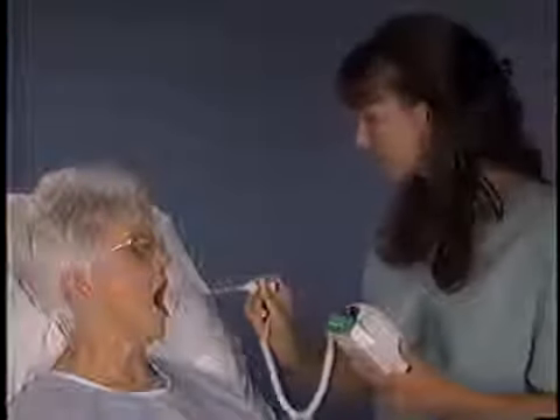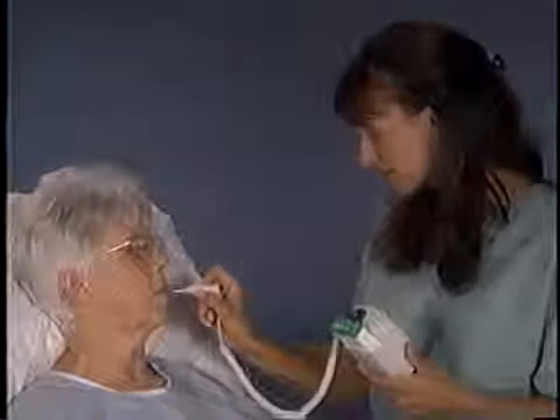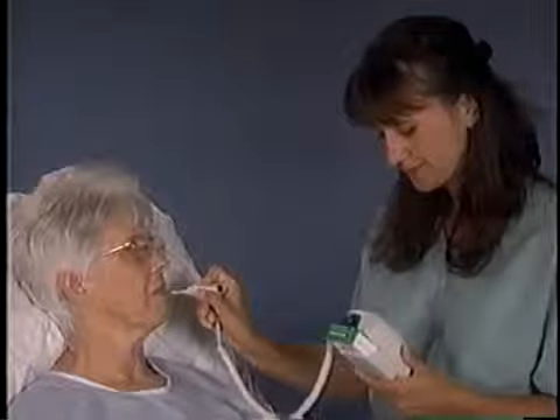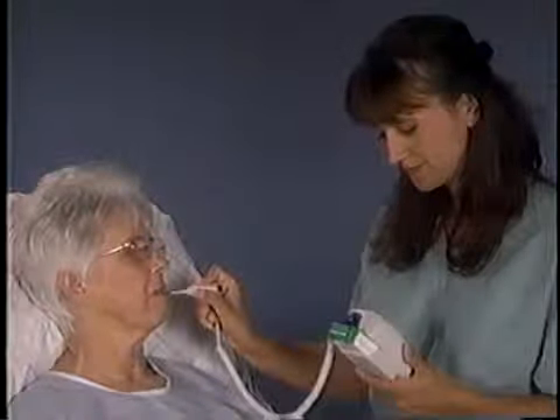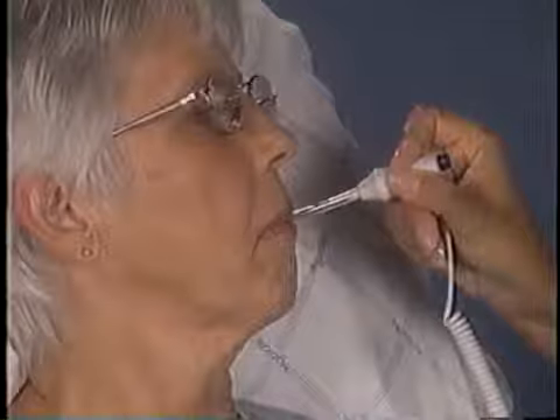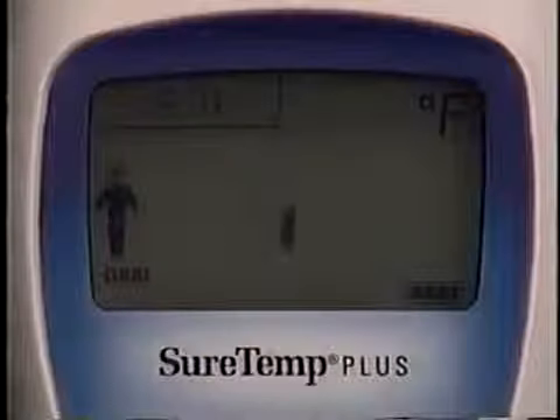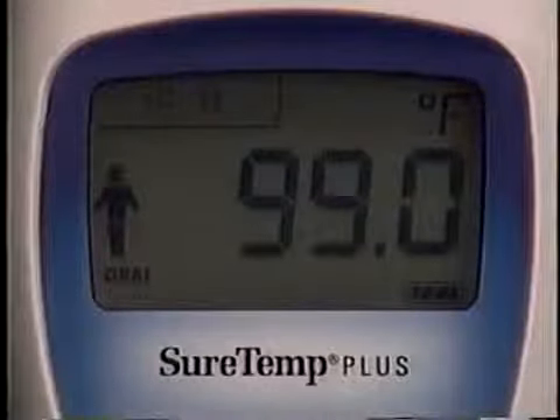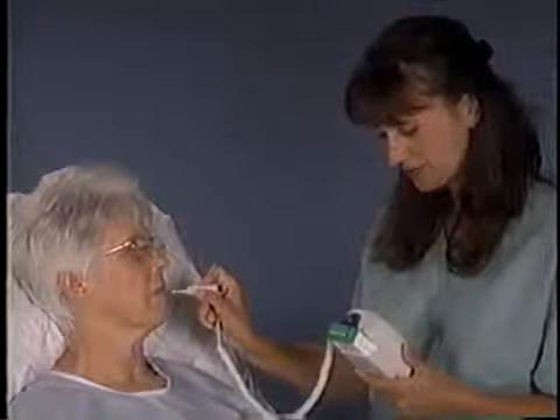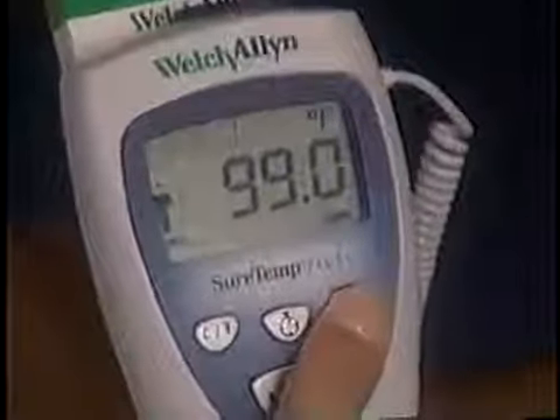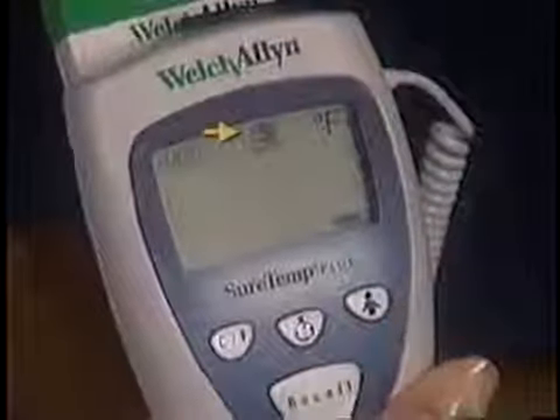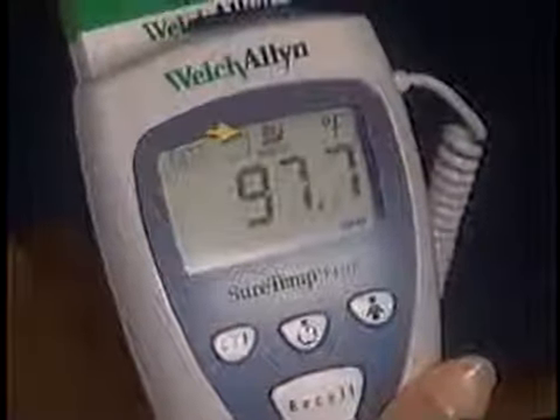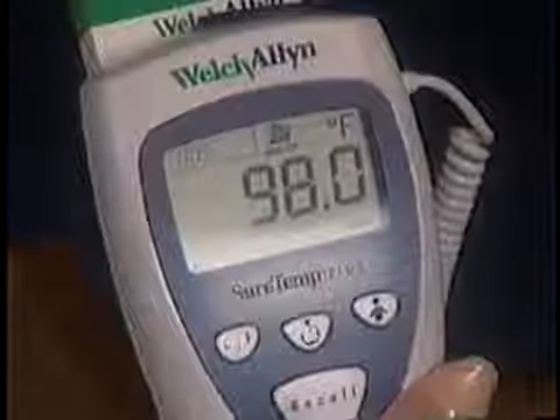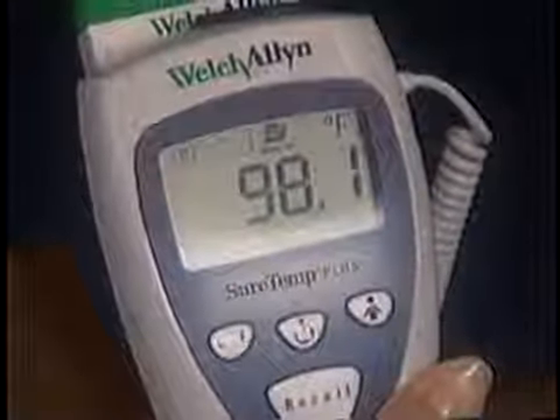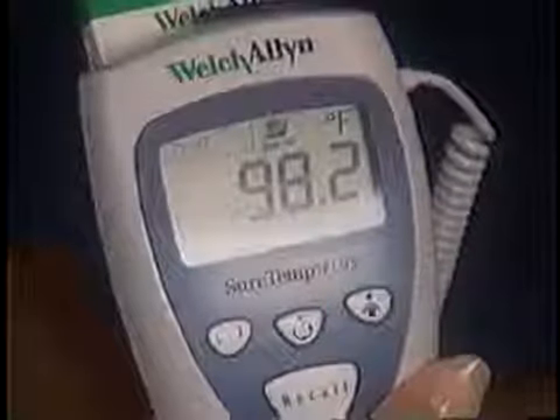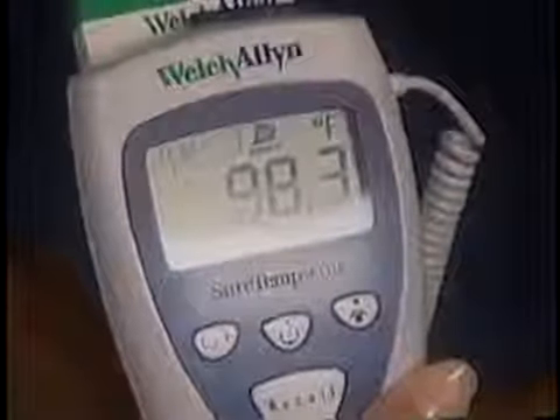Place the probe in the patient's site, following the directions mentioned earlier in this program. Hold the probe in place during the entire temperature measurement. When a final predictive temperature has been reached, the unit beeps and the temperature displays. Hold the probe in position and press and hold the Mode Selection button until the Monitor Mode indicator appears. Keep the probe in place for the required amount of time for the selected patient site. Continuous monitoring beyond 3 to 5 minutes is not recommended in any mode.